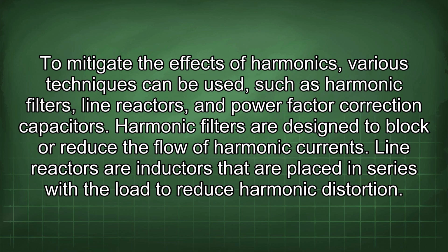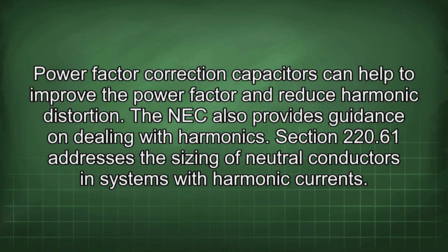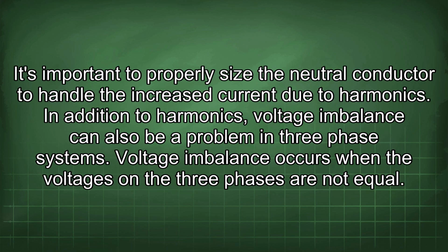Harmonic filters are designed to block or reduce the flow of harmonic currents. Line reactors are inductors that are placed in series with the load to reduce harmonic distortion. Power factor correction capacitors can help to improve the power factor and reduce harmonic distortion. The NEC also provides guidance on dealing with harmonics. Section 220.61 addresses the sizing of neutral conductors in systems with harmonic currents. It's important to properly size the neutral conductor to handle the increased current due to harmonics.